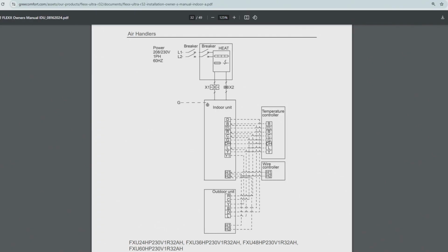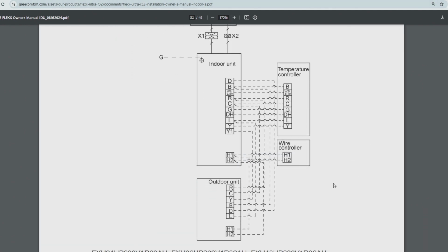Okay. So I'm going to refer back to that wiring diagram again on our website so that we can talk about this and have a wiring diagram in front of us. Okay. So the way this works, if you look at the outdoor unit D terminal, that's going to the D terminal on the indoor unit. Then you also have your W2 auxiliary from the thermostat to the indoor unit. The way the system's supposed to work is if the heat pump is the only thing running and it goes into defrost, that means you are not going to have 24 volts on the W2 auxiliary on the indoor unit coming from your thermostat. So when D is energized on the indoor unit, the fan should shut down.